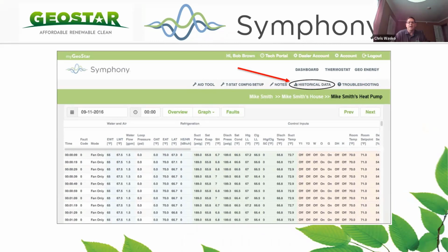When you have the energy monitoring, the refrigerant monitoring, and the performance monitoring added in, the unit is uploading the entire operation of its data points into a cloud, which we call Symphony, every 10 seconds. Pretty much a live operation version that you can log into as a dealer remotely and see a unit in every aspect of what's going on: what the thermostat inputs are, what the heating and cooling is, what's going on with the water loop temperatures, refrigerant temperatures, outdoor air temperatures, and see what position the unit is running in at the very current moment that you're watching it. You can even put it in test mode from here remotely and have the unit running from wherever you're at.